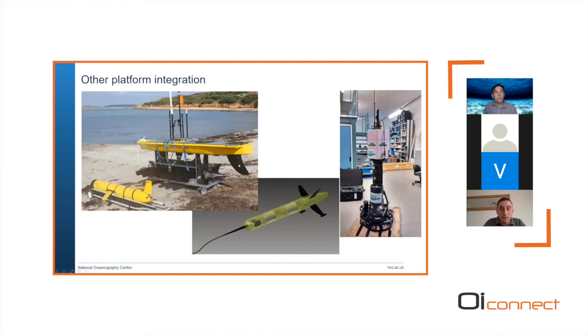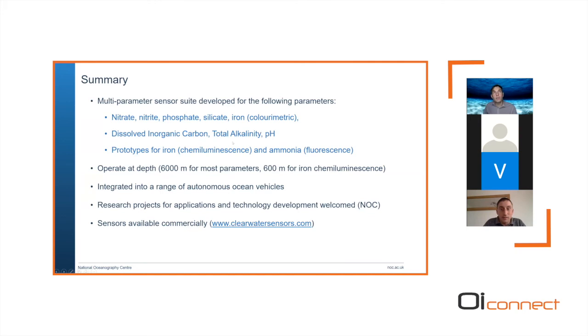So in summary, we now have a multi-parameter sensor suite developed for nitrate, nitrite, phosphate, silicate, and iron, dissolved inorganic carbon, total alkalinity, and pH. And we've got some pretty mature prototypes for trace level iron and ammonia. These can operate to depths down to 6,000 meters for most of those parameters, 600 meters for the chemiluminescent iron platform. They've been integrated into a range of autonomous vehicles, and there's good protocols for doing that.